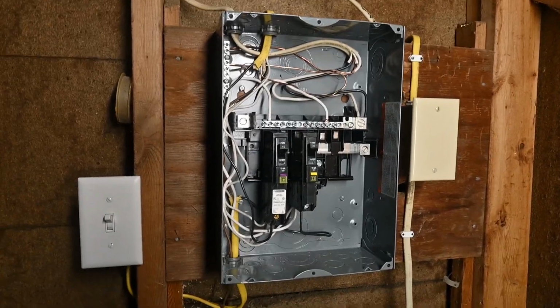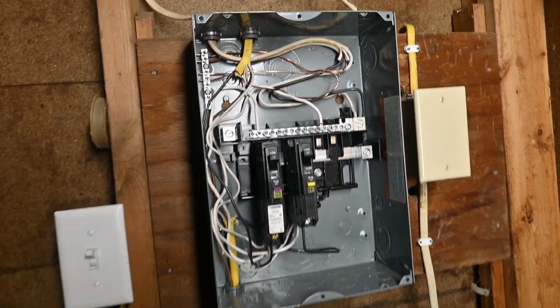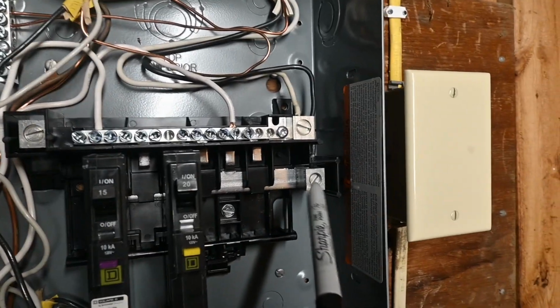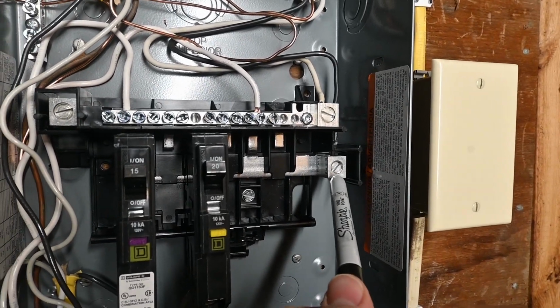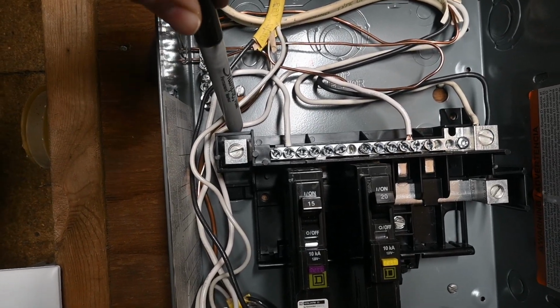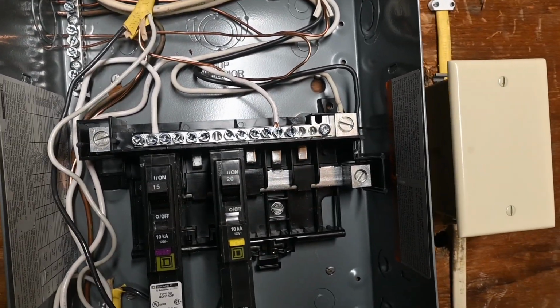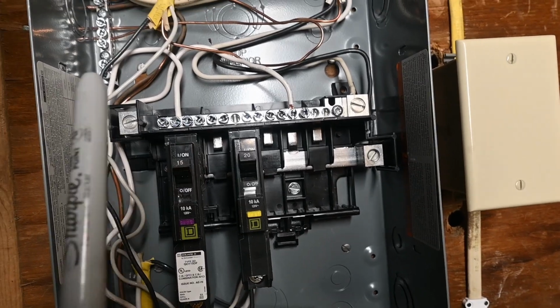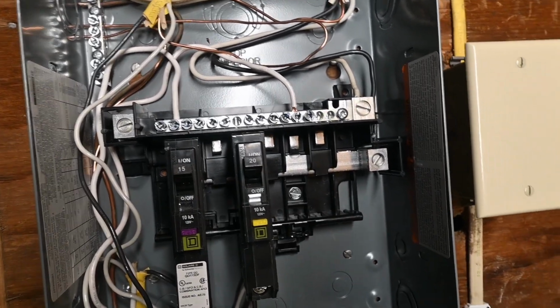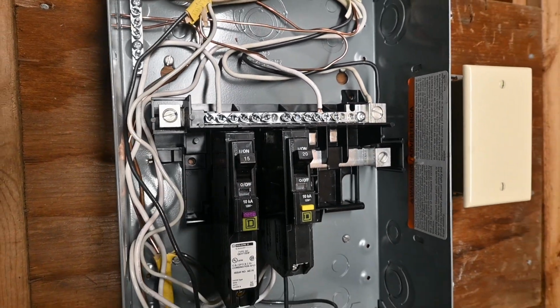Alright, the next thing I want to talk about is how we can actually make all 6 of the spaces in this panel work on a 120 volt circuit. And all that we would have to do in order to make that happen is to put a jumper from here, from this leg that's currently connected, over to this other leg over here. And that would cause there to be 120 volts available on every one of these slots. We just wouldn't have 240 volts available.